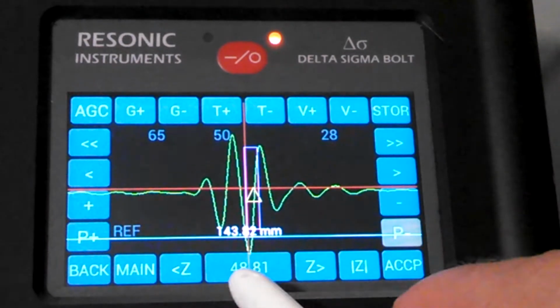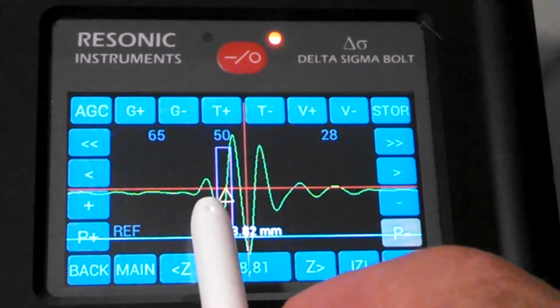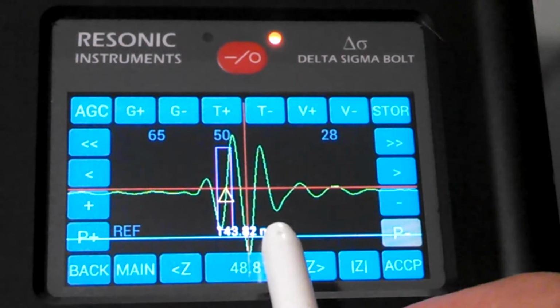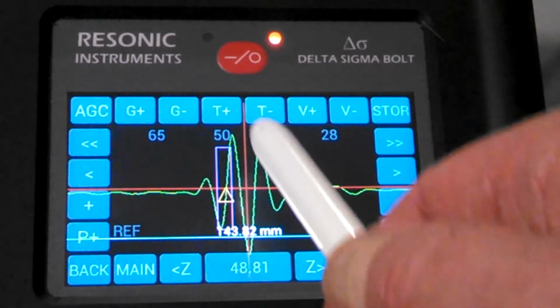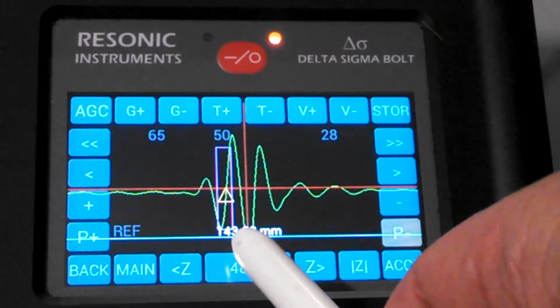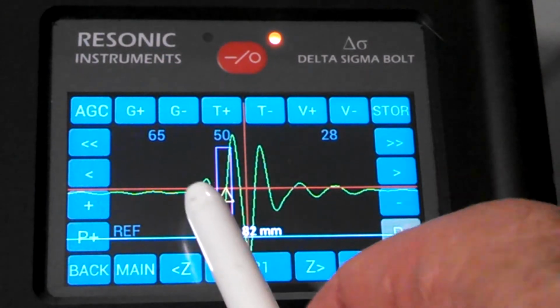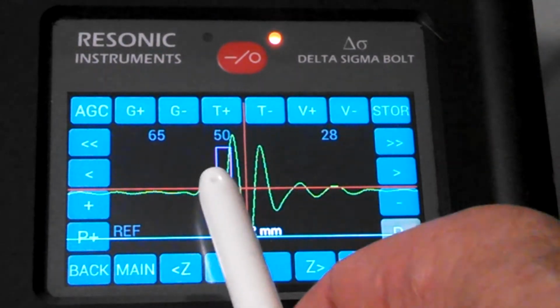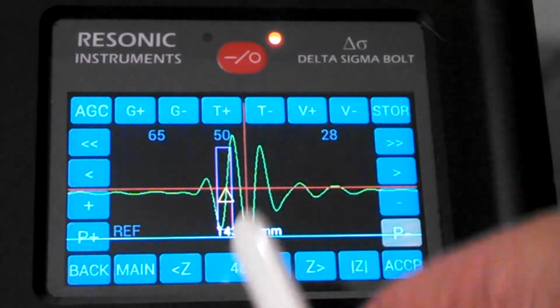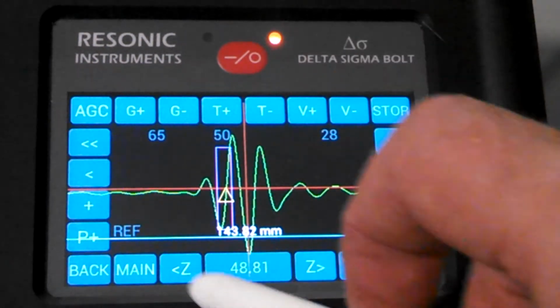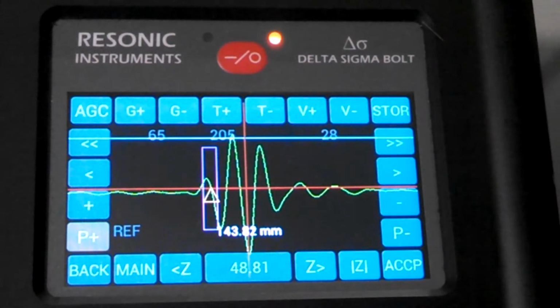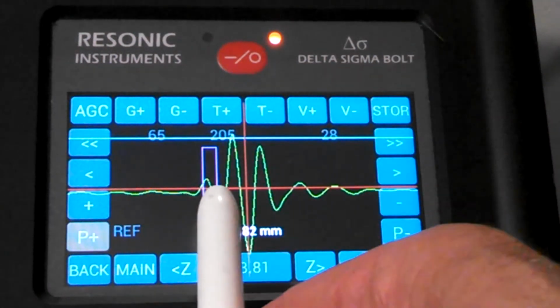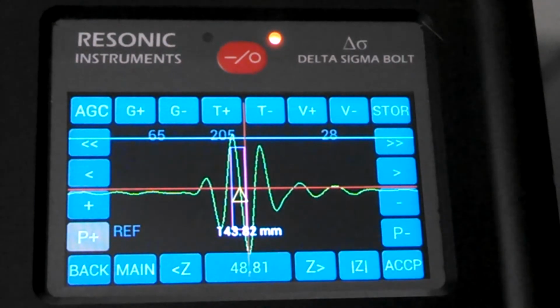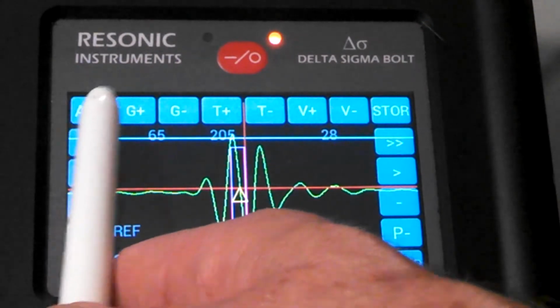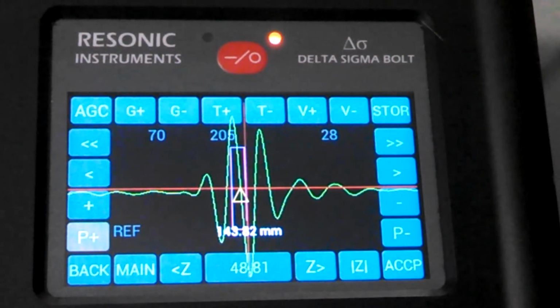So let's move the Z bar back. Now we're triggering the first negative going echo. Our threshold is now 50, and the threshold goes from 0 to 255. So if you're above 128, there's the middle line, and the threshold flips from 50. If I move the polarity back, it goes up to 205 again. But I move the Z bar around, so now we want to get back to the signal. Now, AGC works in this screen, so we want to adjust the signal automatically, and we're back.